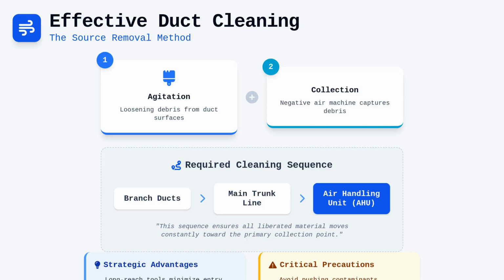the building. In horizontal runs, long-reach tools allow us to clean deep into the system while keeping the entry points to a minimum. Remember to always work from the branch ducts back toward the main trunk line or the air handling unit. This sequence ensures that any material liberated during the process is constantly moving toward your primary collection point.